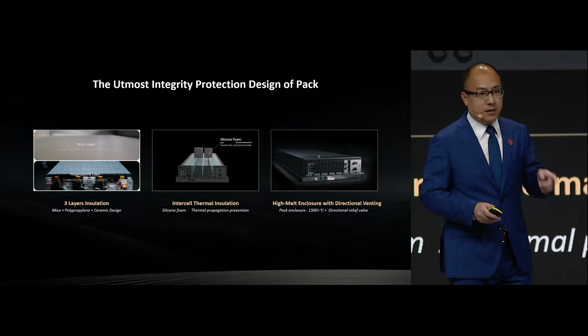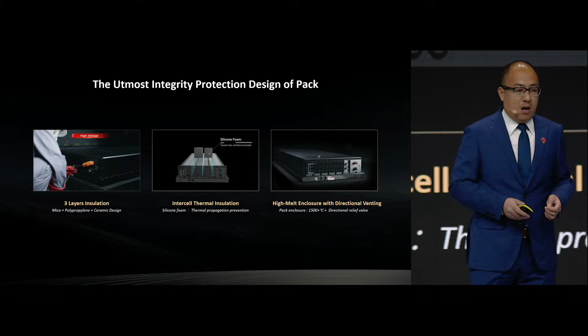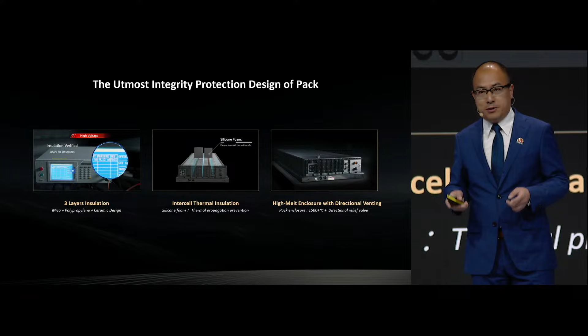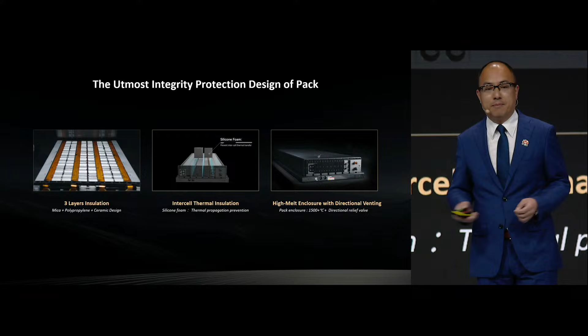Next, we want to show more details from pack to grid. At the pack level, we aim to achieve no deflagration in case of thermal runaway. So we have 3 special designs in the pack. Firstly, we have integrated 3 layers of insulation material between the pack enclosure and the cells. This ensures the pack maintains electrical insulation even in extreme conditions like physical impact, thermal runaway, or high temperature. We have tested under 5 kV voltage resistance in all conditions, and it passed every time.